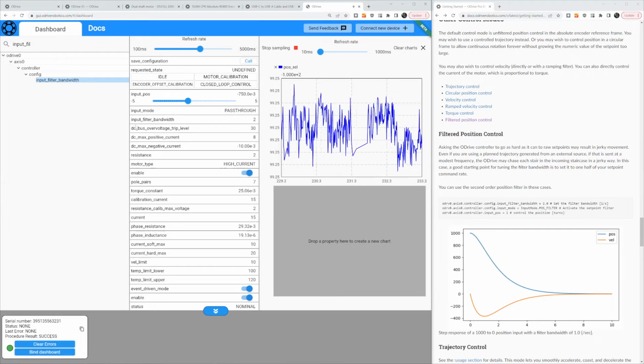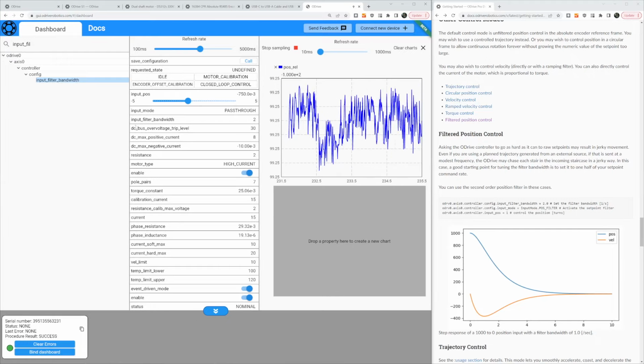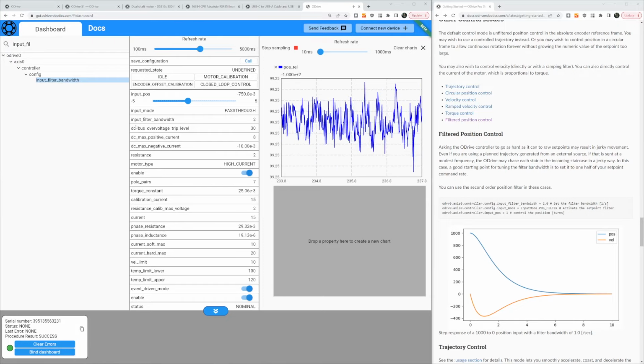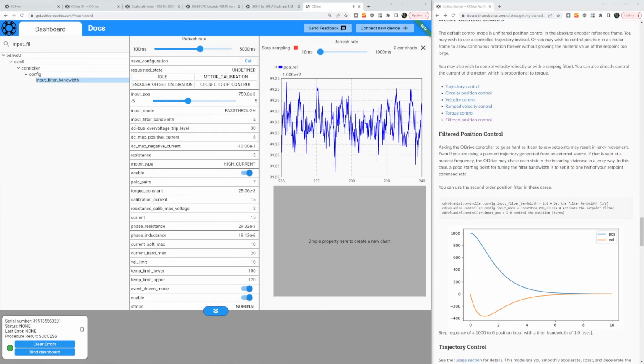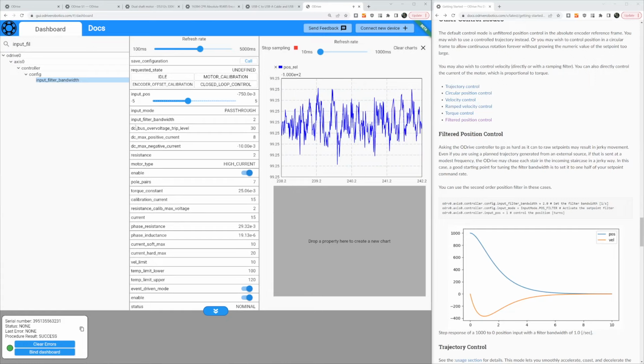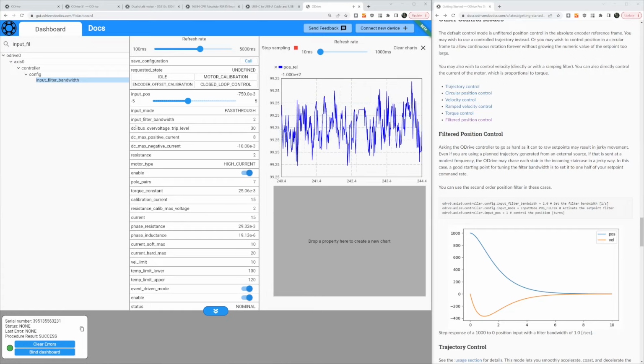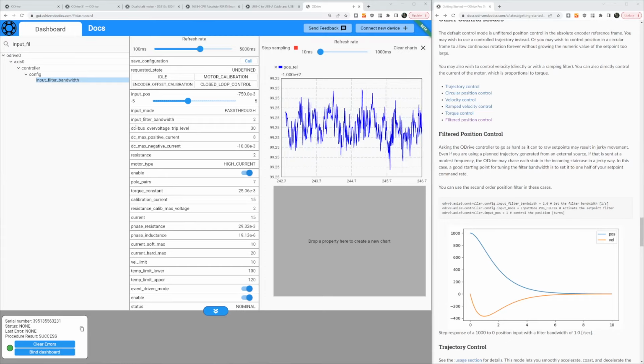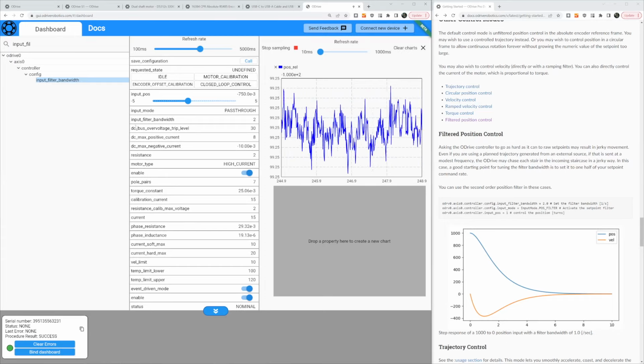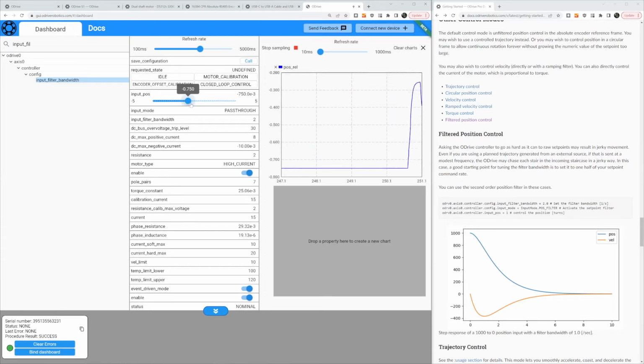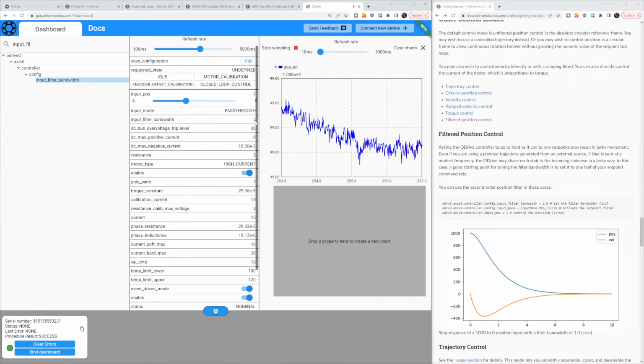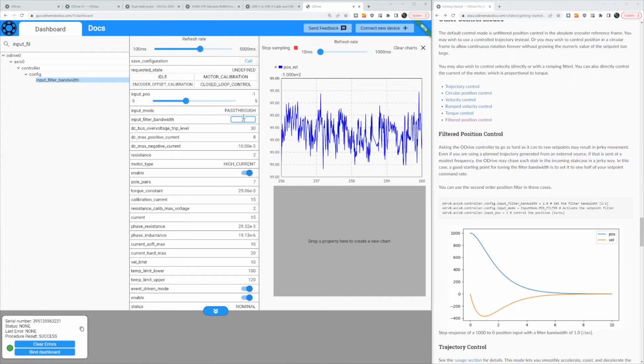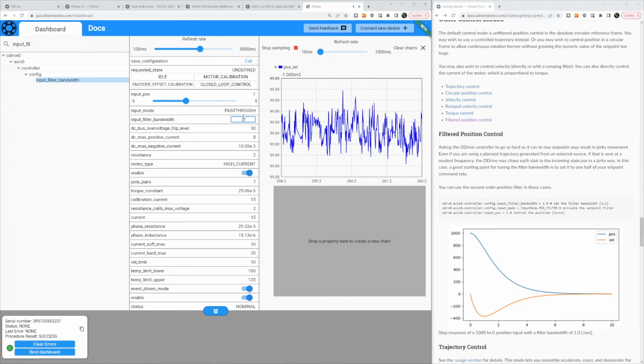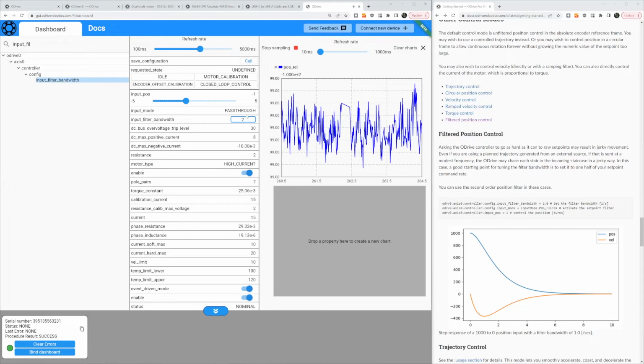In an application where you're sending set point from another module like a Raspberry Pi or an Arduino over CAN, that comes in at some rate, 50 hertz, 100 hertz, that will also cause a stair step like this, but at a much faster scale. That may also want to be filtered. So you can set the bandwidth to filter those—if you send at 100 hertz, you can set the bandwidth to 30, for example.